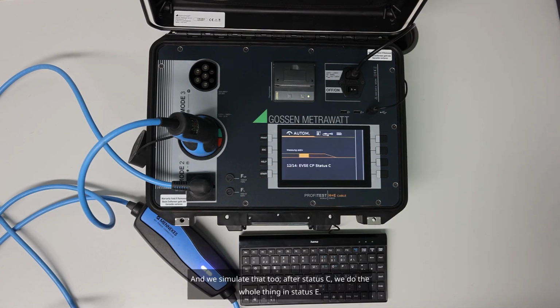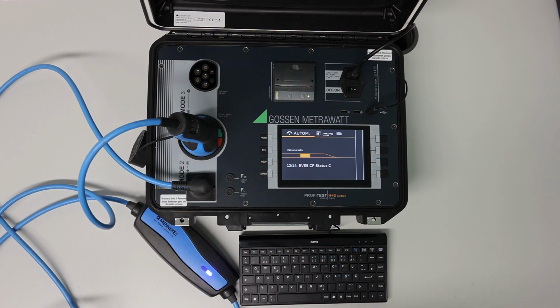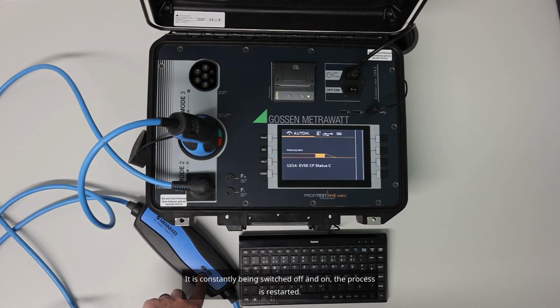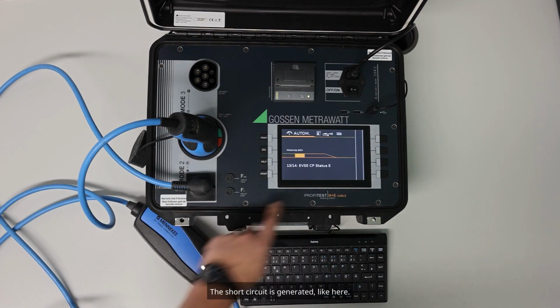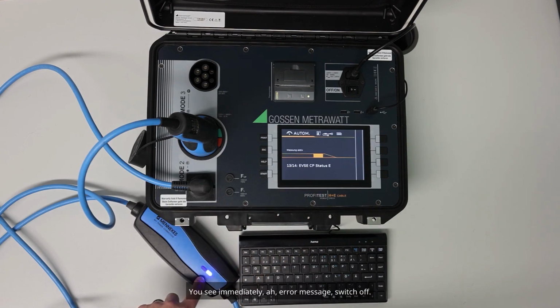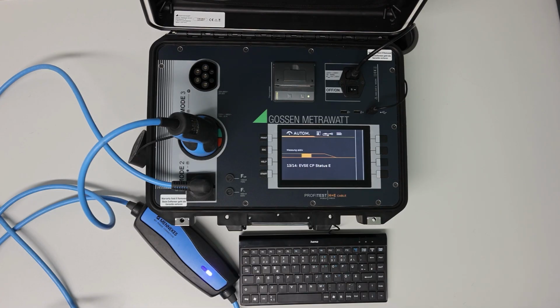After status C, we do the whole thing in status E. And you can see it here again on the charging cable. It is constantly being switched off and on. The process is restarted. The short circuit is generated, like here. You see immediately, error message, switch off. So everything is working. And that will then be reviewed later in the report.